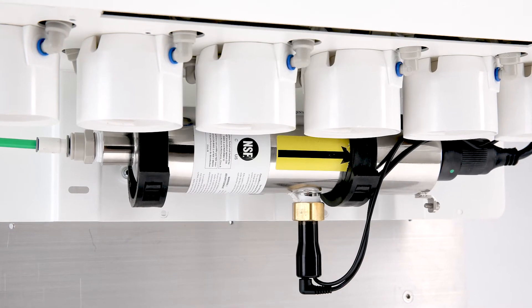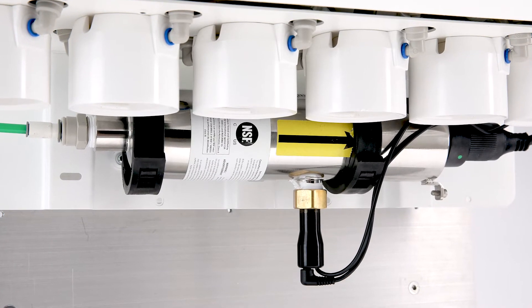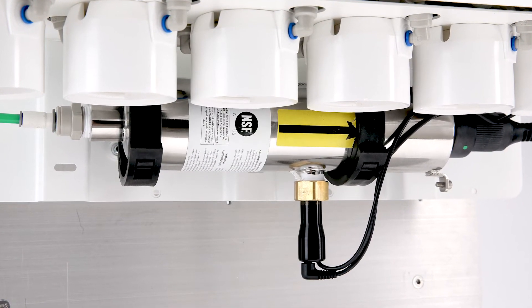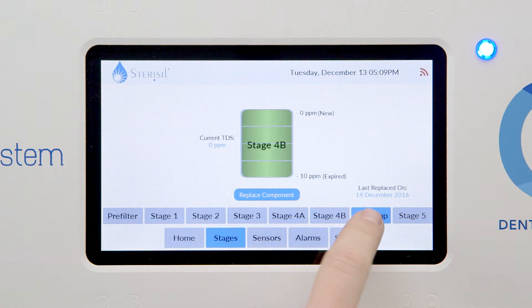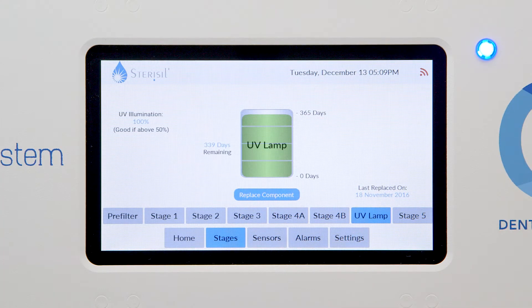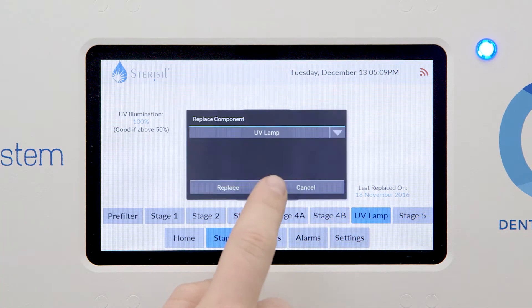The UV light's life is based on both light intensity and a 365 day count. To reset the light monitor, select the UV lamp tab on the bottom row, and then touch replace component.